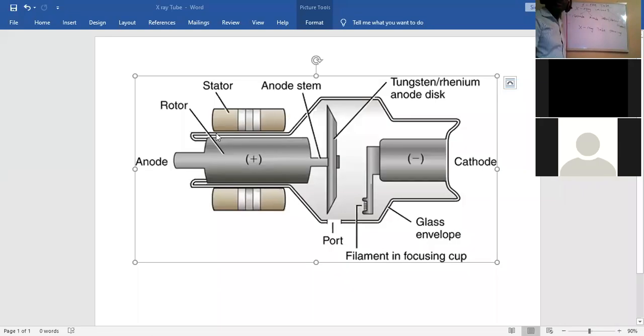Okay, let's use this. The rotor, stator, the anode, and the cathode form the insert. Inside the insert, this assembly and this assembly. This is the support. You have a support here, and this is not the comprehensive diagram anyway.